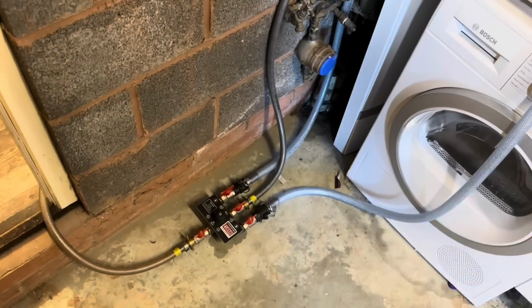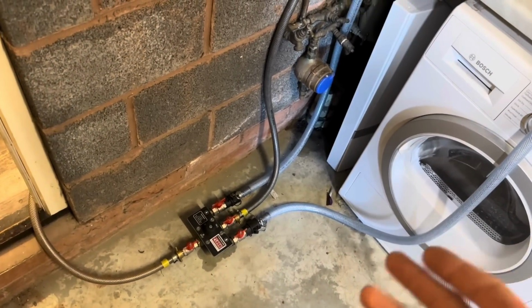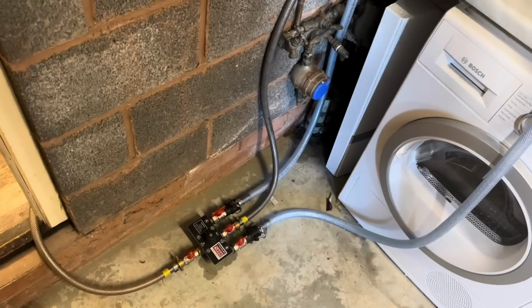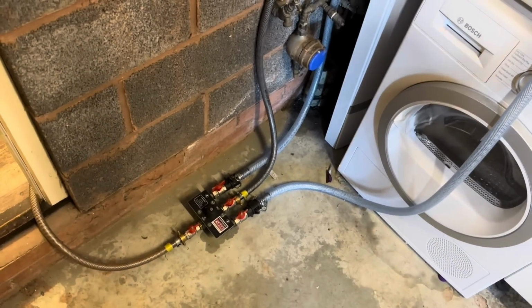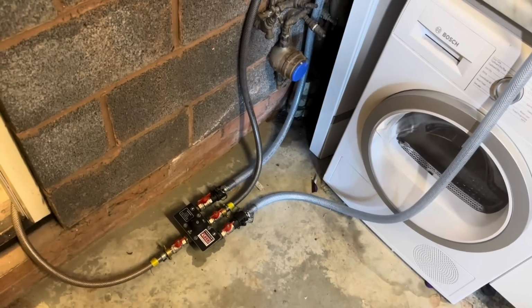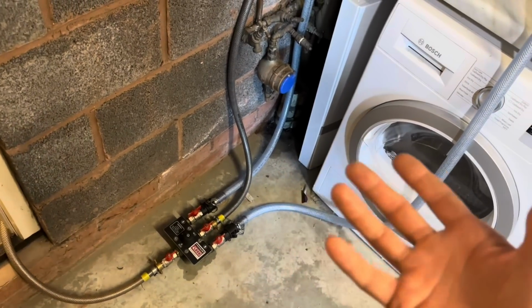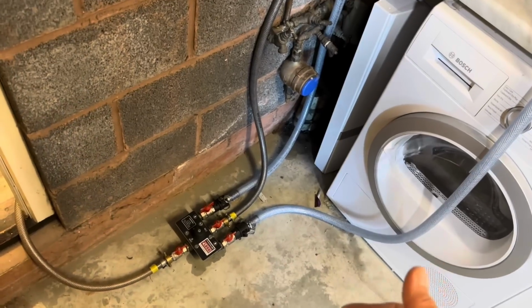It's great. It's cheaper, it's smaller, and we're using mains pressure water to flush out the system. Obviously, you can use a power flush machine. You've got an initial cost of the machine, probably 1,200, 1,300 quid. They're massive, so where are you going to keep it? This goes all into one nice little bag. No chemicals on this one. You have to use chemicals on the power flush.